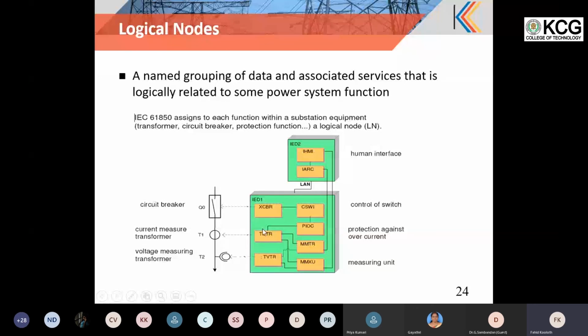Like that, multiple IEDs can be there with multiple functionality, and on the HMI side you can have an HMI or archival function. So there can be multiple logical nodes distributed across the system, and this can be monitored and controlled, and as per the system permission, anybody based upon the permission can perform any action on this. So this is the key concept.